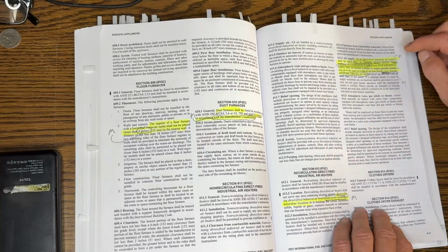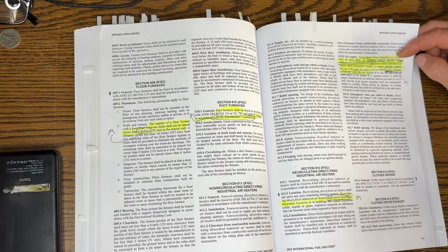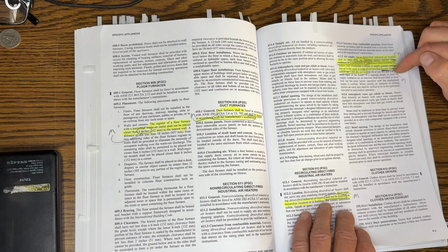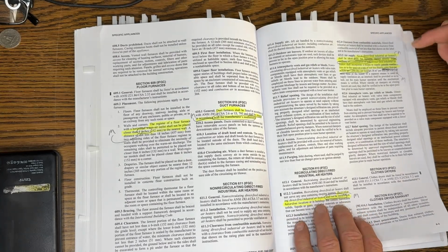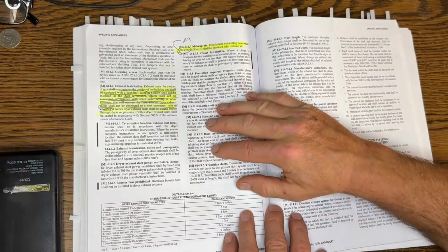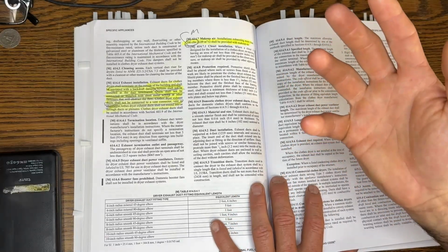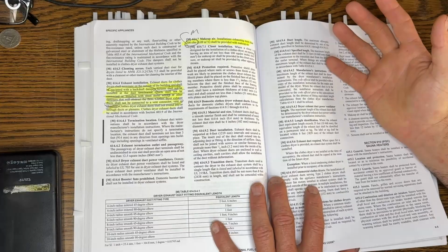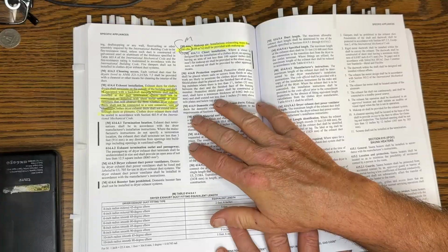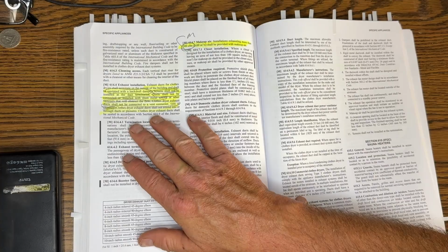Okay, so what you have here, I've seen, you can actually bring in a fuel gas powered like salamander heater into a structure, but you do have to have a certain amount of air changes out capability. So you have to have some openings to the exterior. I've dealt with stuff like this in legacy buildings at work where I do my day job, because you have to have a heater in there. Like your fire protection suppression systems, you always have to maintain at 40 degrees Fahrenheit. So how do you do that if your heat's down? And you could use one of those big gas-fueled appliances, but you have to have outdoor air so nobody dies of carbon monoxide poisoning type thing.